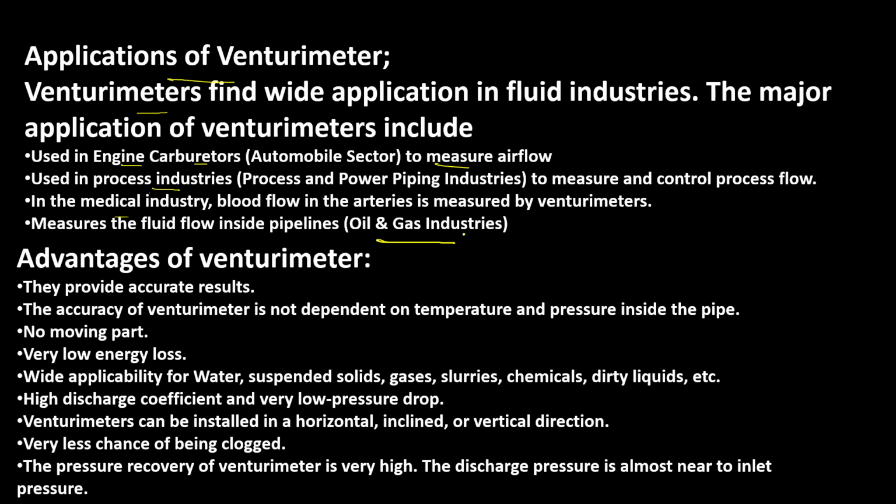After that we will discuss the advantages of the venturimeter. They provide accurate results. The accuracy is not dependent on the temperature and pressure inside the pipe, and it has no moving parts. Very low energy loss, wide applicability for water, suspended solids, gases, slurries, chemicals, dirty liquids, etc. High discharge coefficient and very low pressure drop.